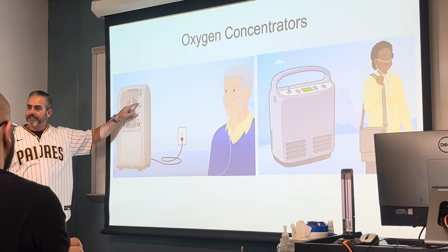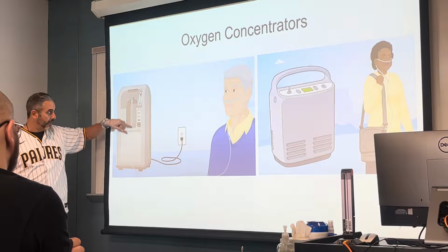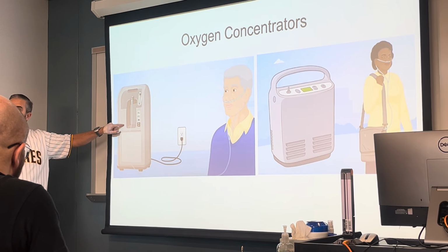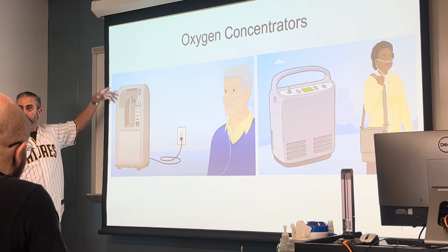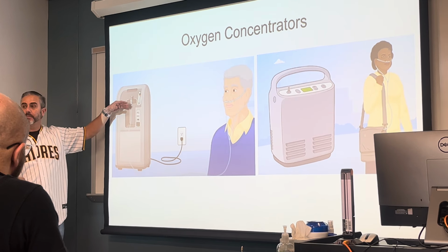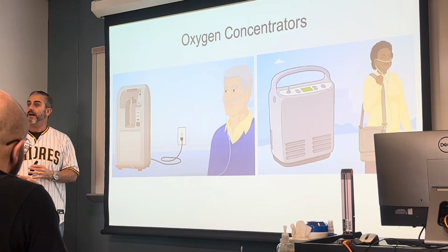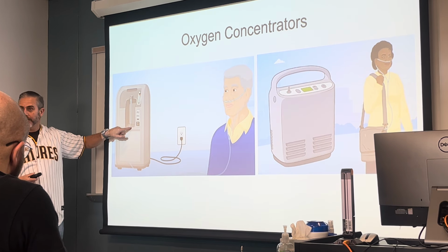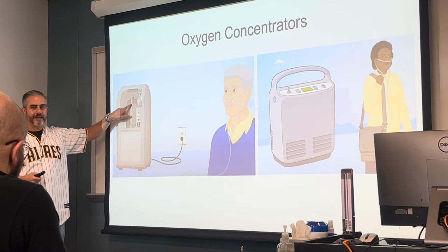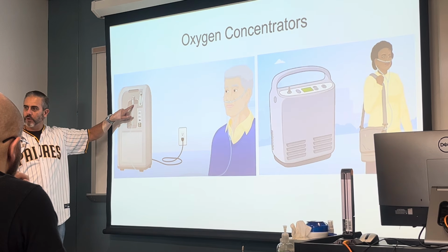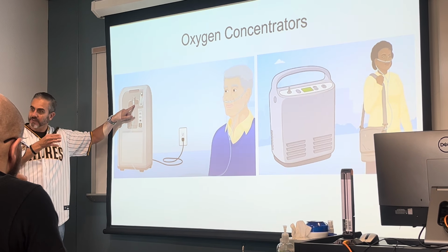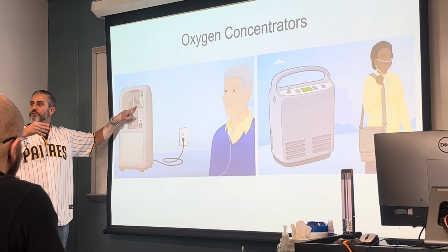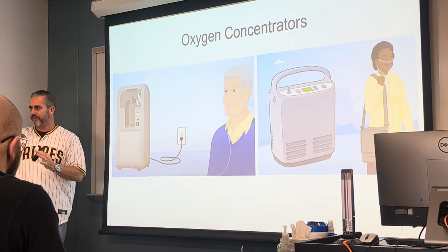Well, the higher the liter flow you turn this on, meaning the more oxygen or more gas is coming out of this, the harder this has to work. It's going to try to pull more room air in, and it's going to be harder for it to stay up if the flow is going through here so quickly.